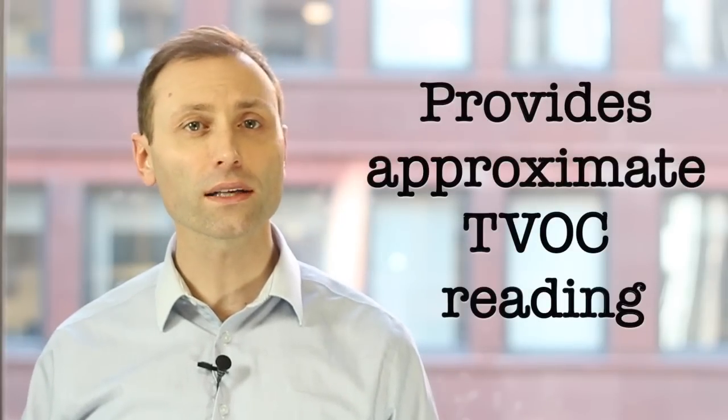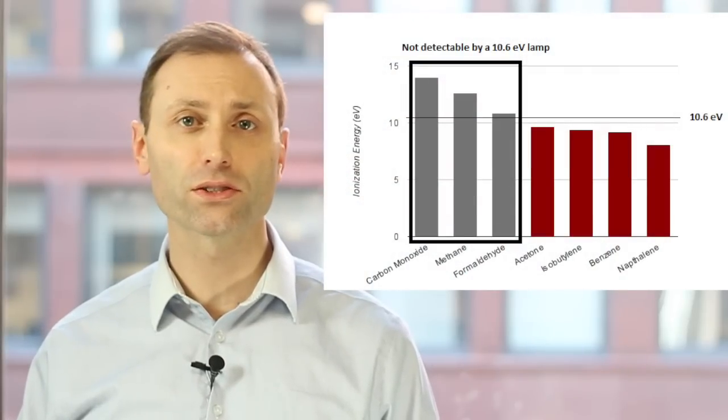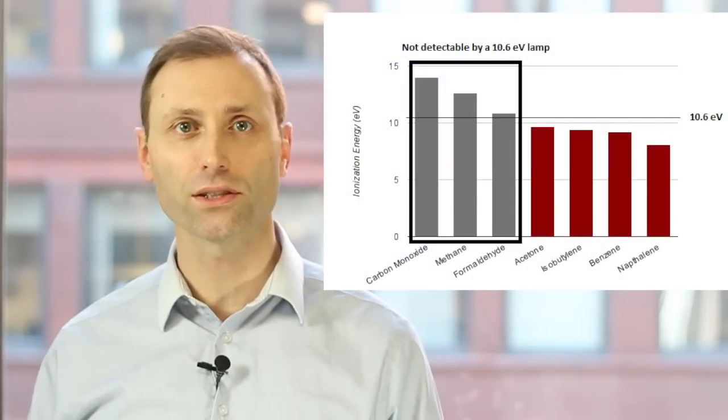Because the PID reading is an equivalent of the calibration gas, the device gives an approximate TVOC, not a true measurement. It's also important to note that PIDs cannot detect all VOCs in the air. This happens when the PID's lamp energy is less than the VOC's ionization energy.